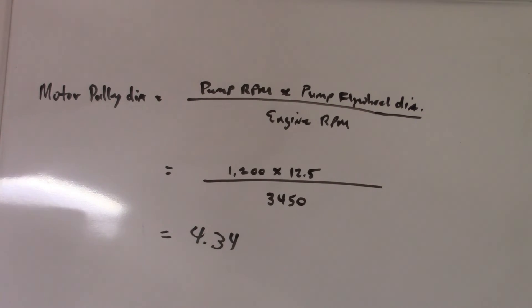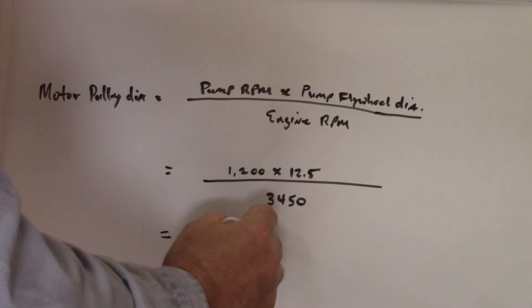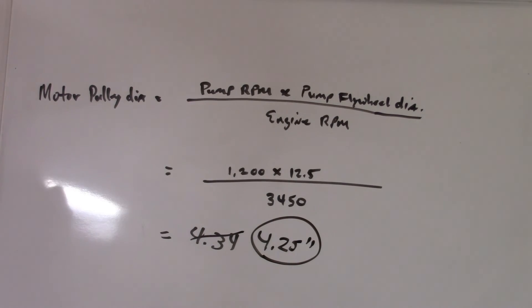A four-and-a-quarter inch pulley gives us 1173 pump RPM — that's what we need. So we just need to figure out what shaft size the motor has, take the existing pulley off, and go with a four-and-a-quarter inch pulley to get us down to the correct pump speed.